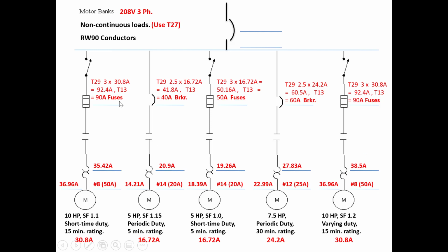Okay. So once we have all these, now we've got to look at the top of this overcurrent. So we have a breaker coming here. So 2 of these are breakers already. But if this main is a breaker, we need to get all of these sized as if they were breakers in order to compare. Again, if we want to compare all these, which is what we're going to do, we have to have a benchmark. So they all have to be the same type of overcurrent so that we can compare them properly.